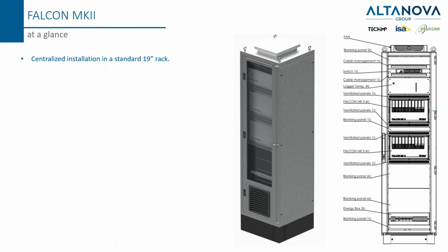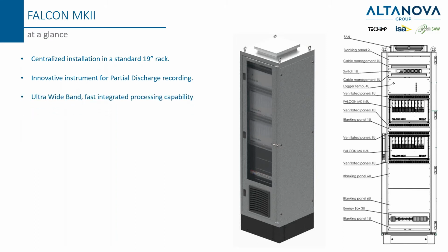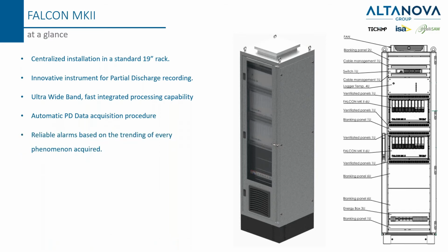Basically, some highlights of the system: the centralized substation installation is inside a standard 19 inch rack. The instrument is innovative for partial discharge recording, with ultra-wideband fast integrated processing capability and automatic partial discharge data acquisition procedure. So again, the system is totally automatic. It can provide reliable alarms based on the trending of every phenomenon. And as we mentioned at the beginning, it is a comprehensive solution that can integrate other modules and systems.